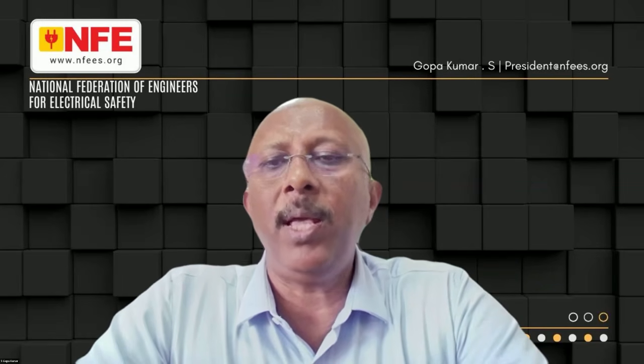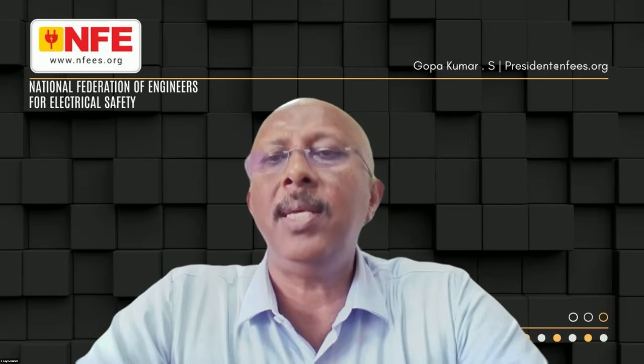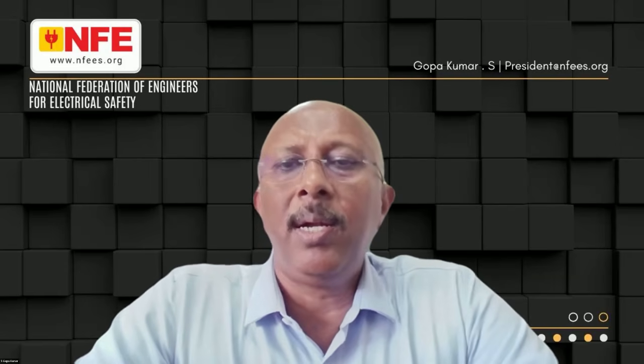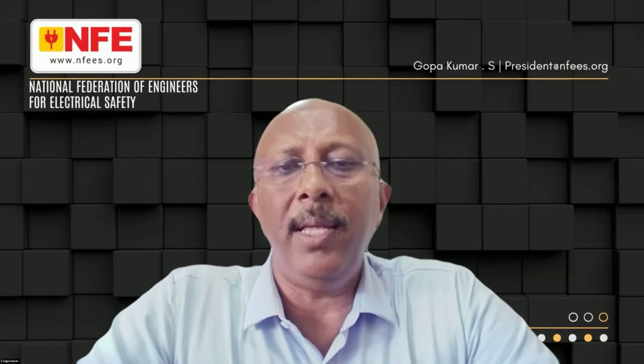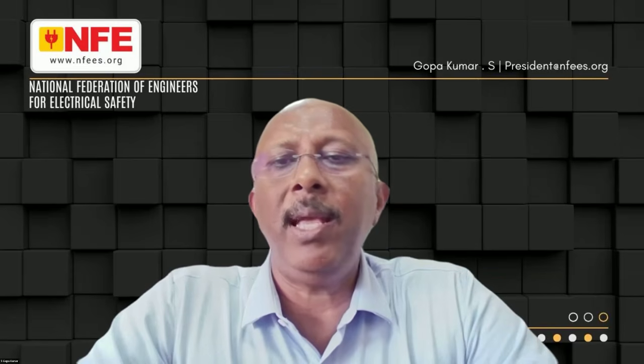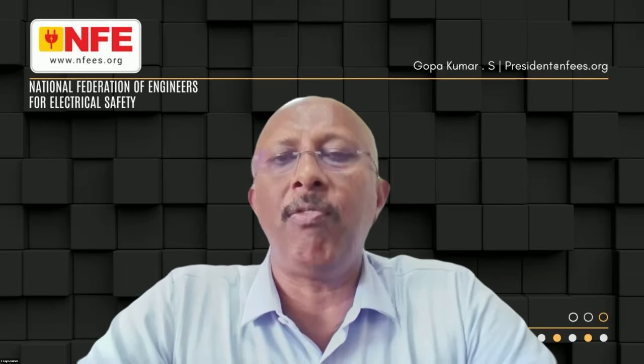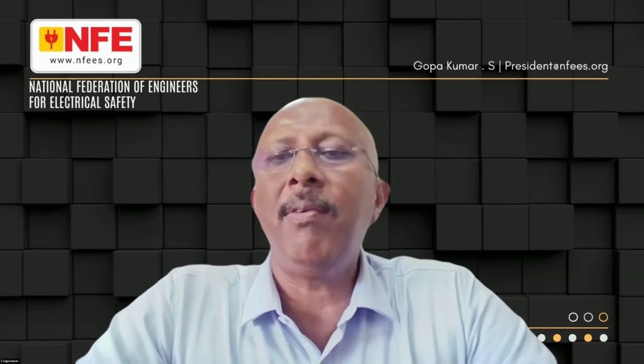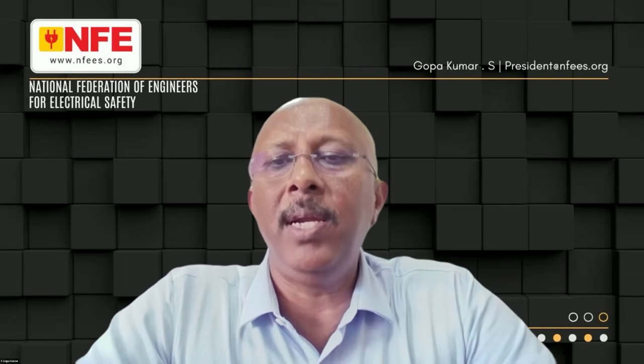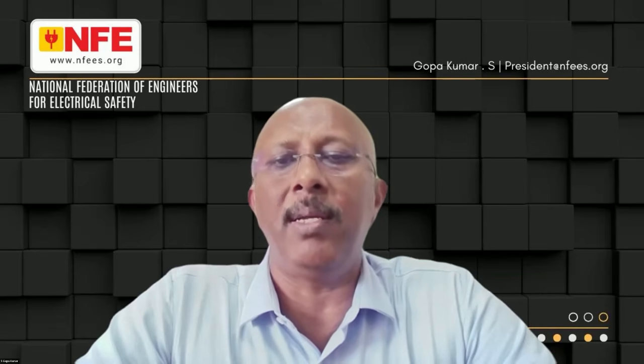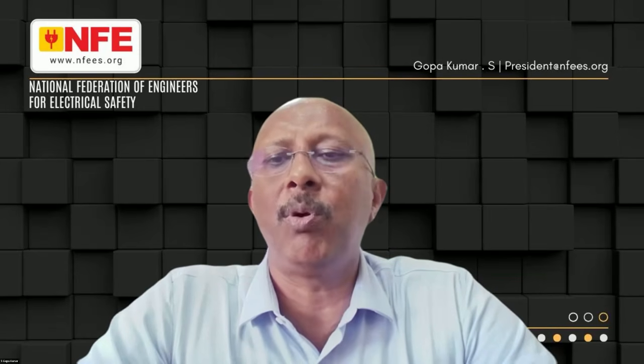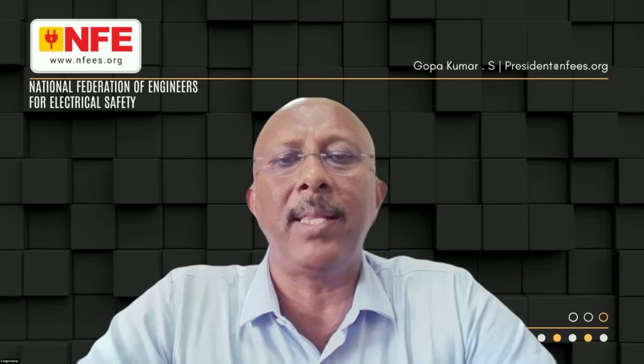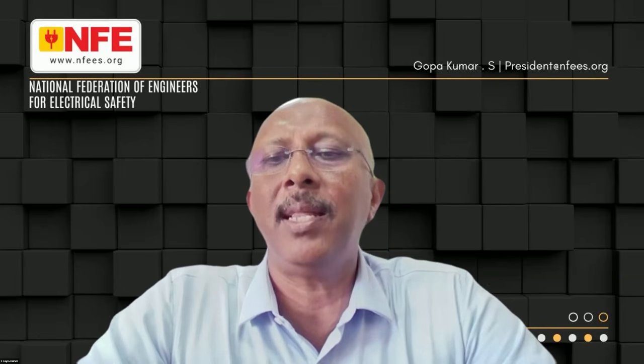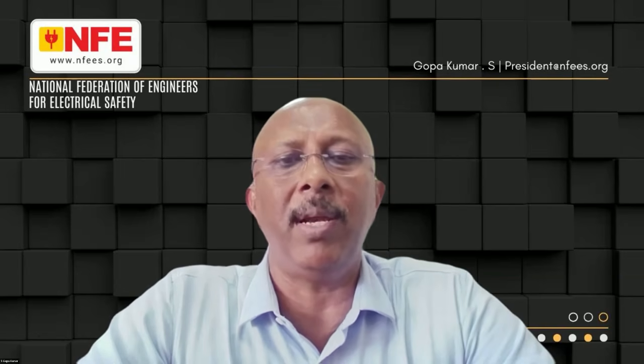Now, if you put an AFDD, please seriously look into the technical parameters of the AFDD. If you put an AFDD in a circuit which is taking a current of, let's say, 0.5 amperes, the AFDD will not work. AFDD requires some minimum current to operate. I think it is about 2.5 amps or something like that. If the circuit current is lesser than that, the situation is different.